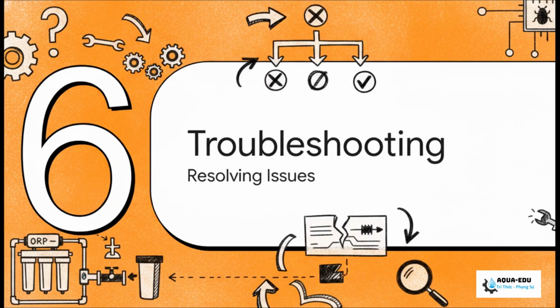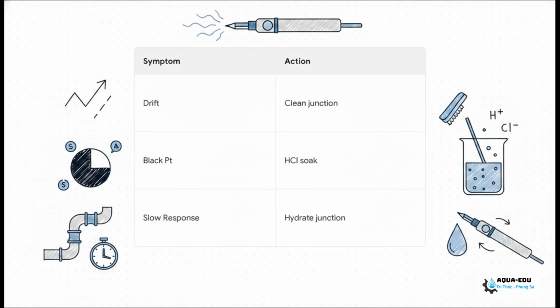And if things go wrong, we move to Phase 6. Our troubleshooting guide. Listen, things will go sideways eventually. If you start seeing drifting readings or notice a blackened platinum ring, which is usually caused by sulfide poisoning or organic adsorption, your very first line of defense is cleaning that reference junction or performing that 15 to 30 minute soak in 1 molar hydrochloric acid. If the response time is just incredibly slow, the junction might just be dry and needs to be rehydrated in potassium chloride or DI water. And if your reading is just wildly fluctuating around 0, you've probably got a broken cable or an oxidized connector on your hands.